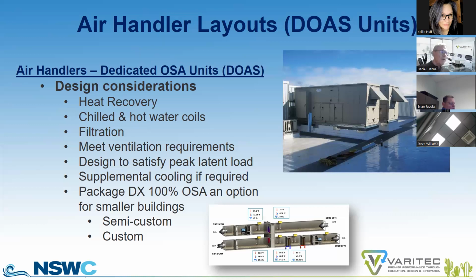What is the air change rate of outside air to a building necessary to secure good indoor air quality? Well, I'm hearing through ASHRAE, though I validated last week with a 62.1 board member, that though there are many studies going on right now assessing what is a good air change rate, nothing has been definitive yet, and we don't know what that is. We're going to hear probably a good design will require 2 to 3 air changes per hour. Optimally, I've read as much as 4 to 6. Regardless, there's an energy penalty for that enhanced outside air. So you want to make sure you have the heat recovery solutions in place to reduce the load on a cooling coil at those outdoor air flow rates.